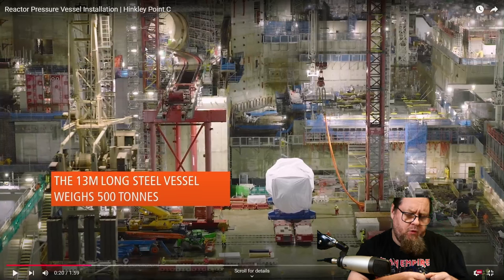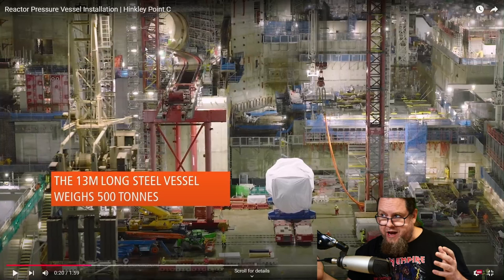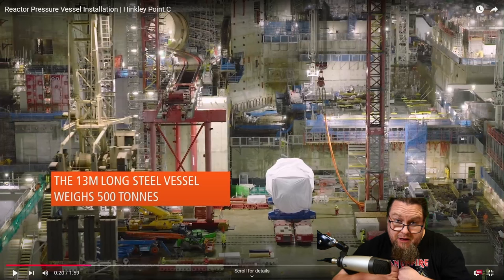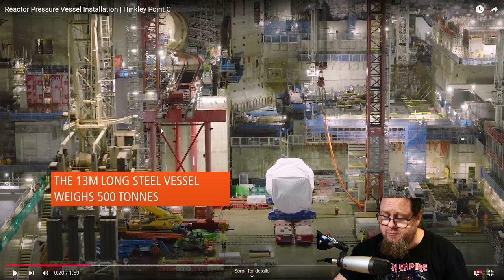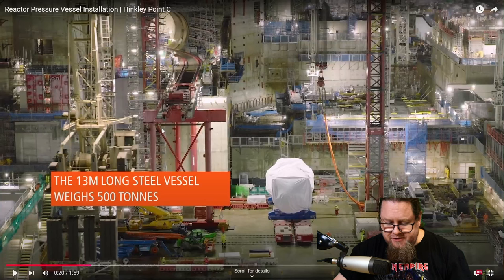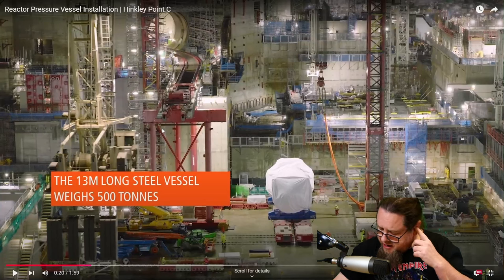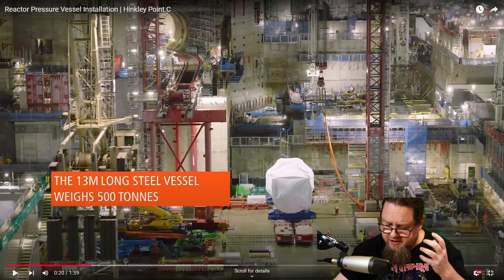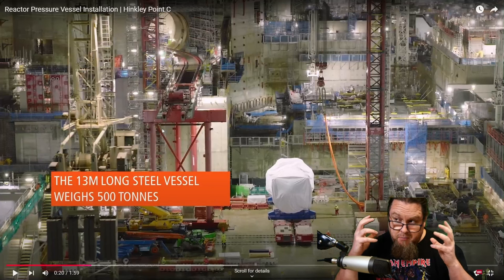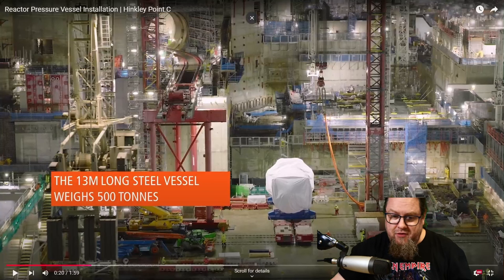The reactor containment building itself operates at a slight under-pressure, which means that if there were any leak somewhere, air from the outside would be sucked in instead of air from the inside being pushed out. I've witnessed this at the Borssele nuclear power plant. I have a sensitivity to pressure differences, and when you get into this pressure lock and the pressure decreases, my ears started popping like crazy. That's one of the notable things about these containment buildings.